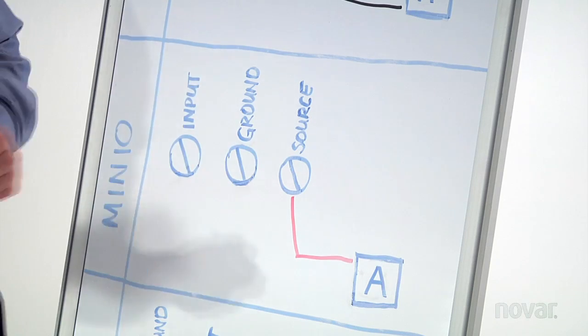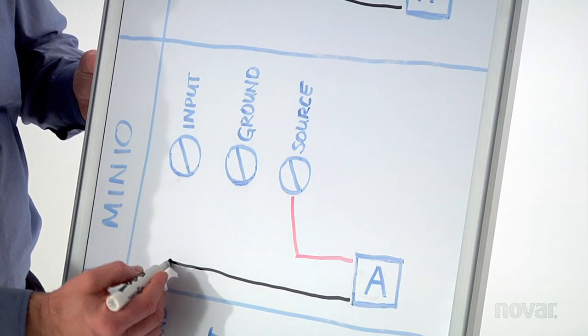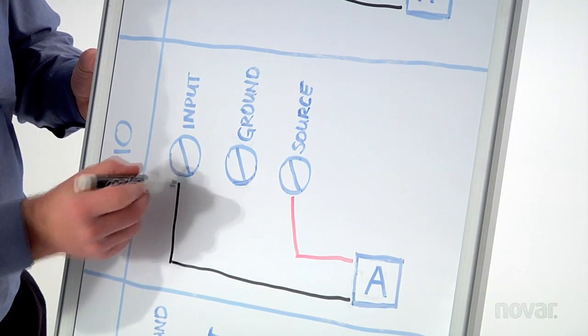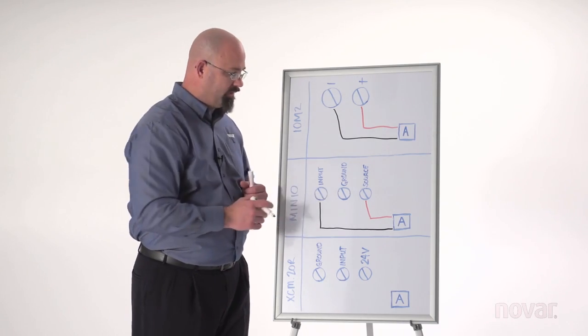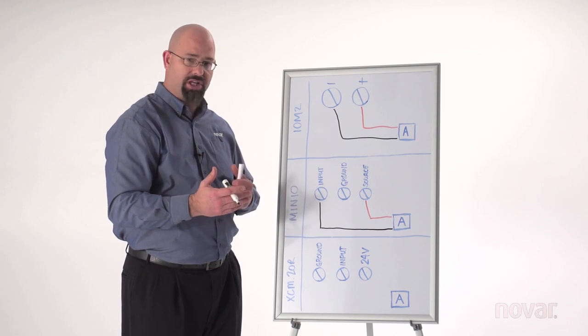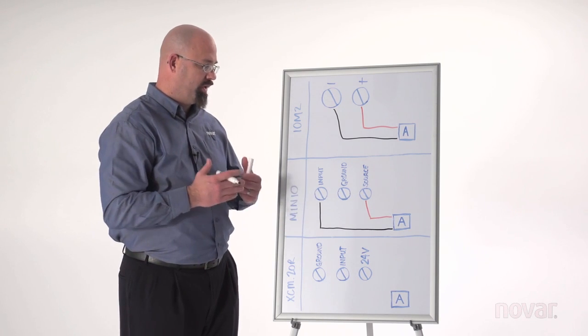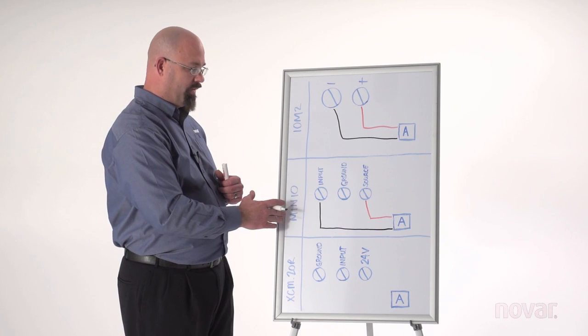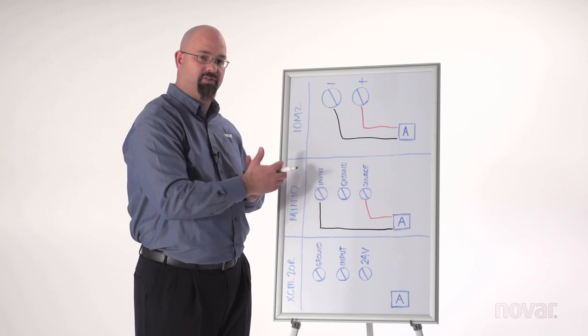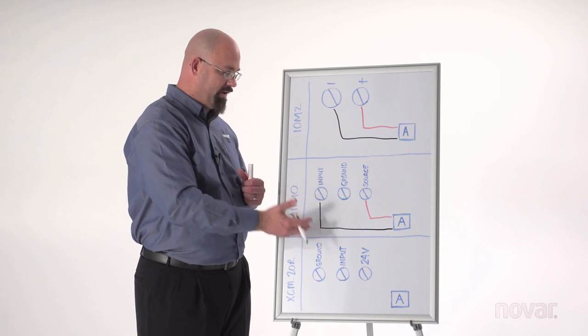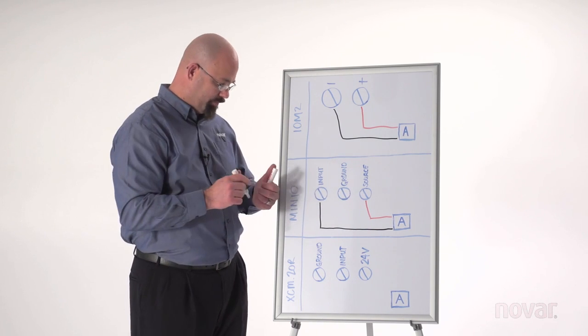From the negative side of that sensor, I'll bring the NOVAR black wire back to the input terminal so it can receive that analog value. Now on the MinIO, that analog value can be a 4 to 20 milliamp or a 0 to 10, or a range within 0 to 10, meaning 1 to 5 or 1 to 10, as long as it's within 0 to 10 range. Remember on the MinIO, on those universal inputs, I have to move that input specific jumper between I for 4 to 20 milliamp or V for 0 to 10 volts. But where it gets its power from is going to be the source terminal, again in a loop powered sensor.